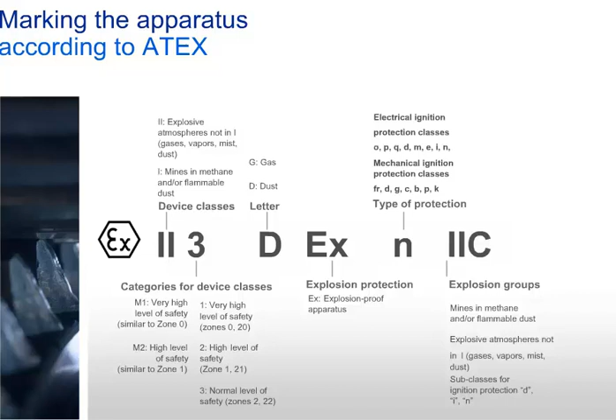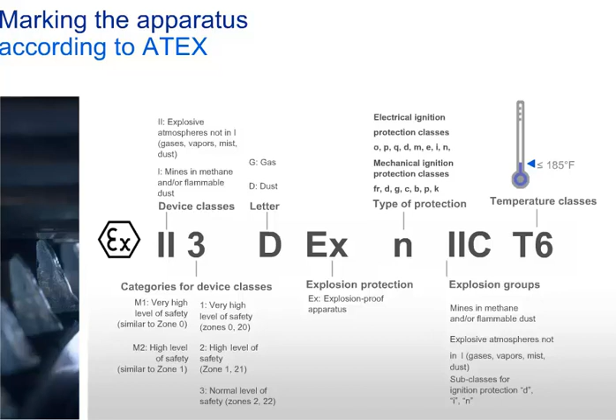T1 to T6 are the temperature classes in relation to the ambient temperatures. Temperature classes in accordance to IEC 60079-0 are T1 less than 842 degrees Fahrenheit, T2 less than 572 degrees Fahrenheit, T3 less than 392 degrees Fahrenheit, T4 less than 275 degrees Fahrenheit, T5 less than 212 degrees Fahrenheit, T6 less than 185 degrees Fahrenheit, where these are the surface temperatures of the equipment.